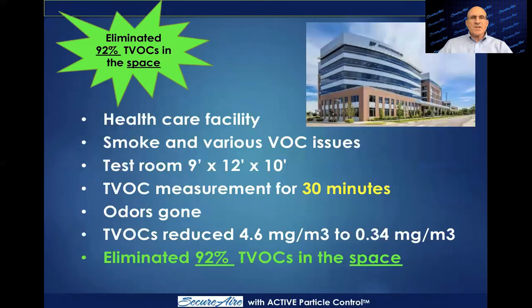In terms of VOCs, we're in hospitals all the time, as you could imagine. In this example, we put a small unit in a test room and measured the VOC level, 4.6 milligrams per cubic meter. Within 30 minutes, we almost eliminated it down to 0.34, or 92% of the VOCs were removed from the space. And the odor that had been prevalent from smoke and body odor and that sort of thing, and that happens in healthcare facilities, has been eliminated completely.